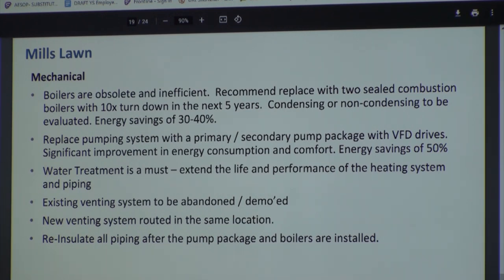Again, for the pumps, I would replace them with a pump package and put VFD, variable frequency drive controls, on it so the pumps can operate at a lower RPM. If you only need 10 gallons a minute, you run the pumps slow. If you need 100 gallons a minute, you run them faster, but you're not running the pumps at high speed all the time. Water treatment is a must.